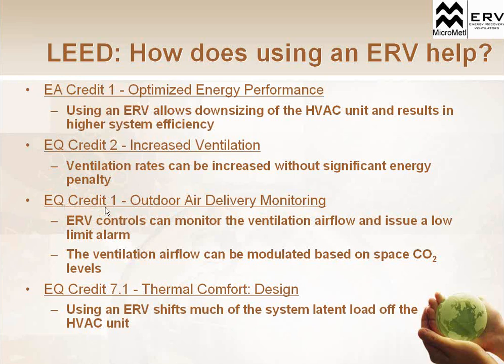If we look at outdoor air delivery monitoring under environmental quality credits, under LEED EQ, with these energy recovery units, part of the built-in controls is that we're going to monitor how much air we're bringing in and exhausting. Therefore, we're monitoring the ventilation airflow going into the building, which is what the standard is looking for. They want to know how much actual outside air is getting into the space. And we can modulate that based on the CO2 level. So based on the number of occupants in the building, we can modulate the amount of outside air we're bringing in.